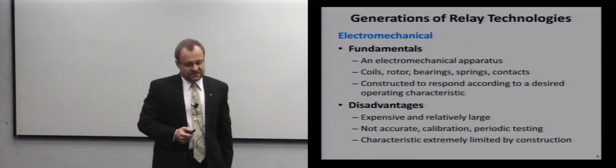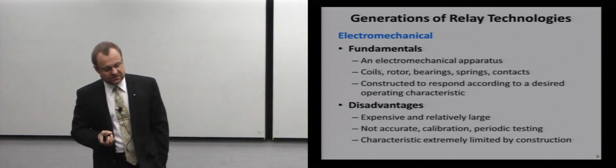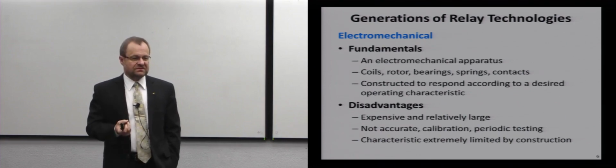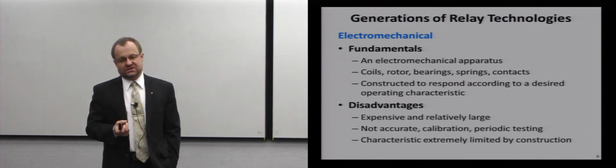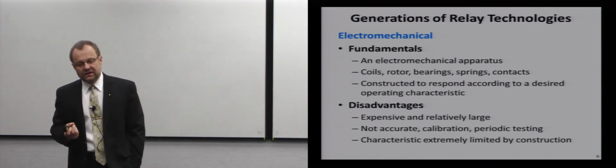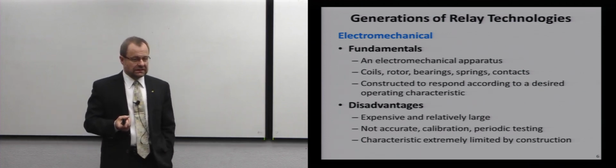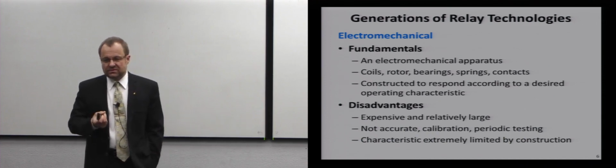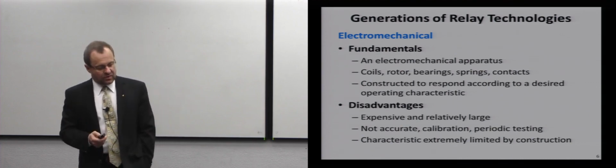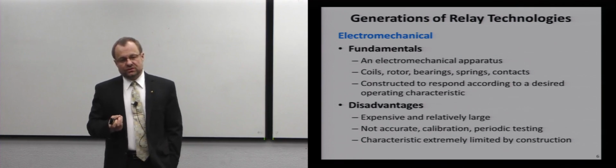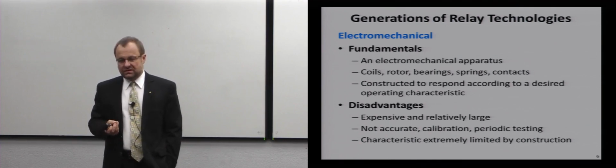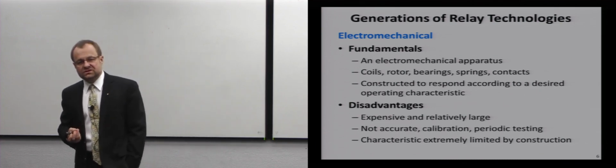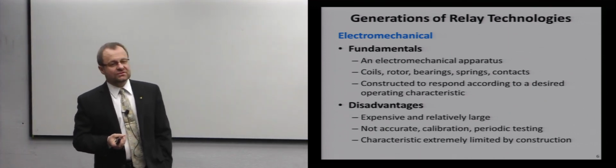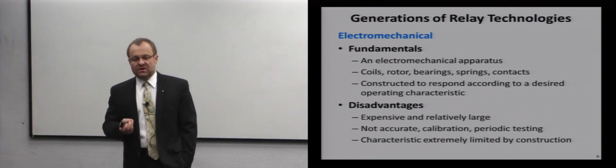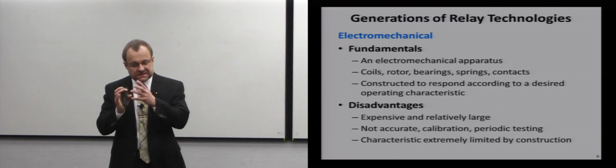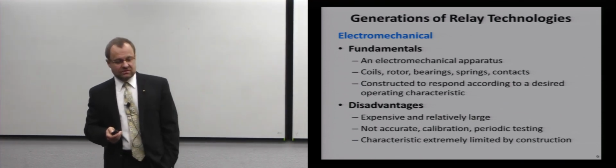Right? So the disadvantages were that those were expensive and relatively large, not accurate because they were not only analog devices, they were electromechanical devices with moving parts. So anything that moves, that has a spring or a bearing, you have to suspect that after a year or two of inactivity, it will get stuck, it will get dirty, there will be dust, there will be rust. How could you trust it? So we have to maintain it in a proper way. And also, what those devices could do was extremely limited by the construction. If you provide something by means of calculations in real time on a microprocessor, whatever you could dream, you could program. Anything is possible. When you are taking pieces of iron and copper and building something that moves, your options are really limited. But that was the technology available then.